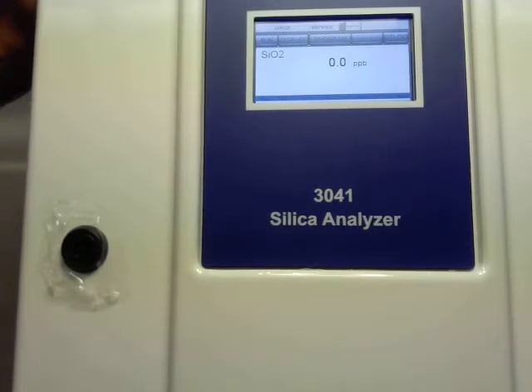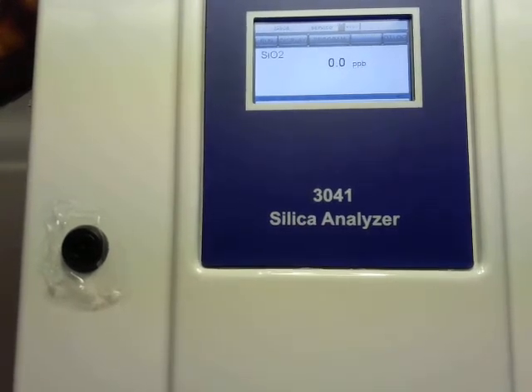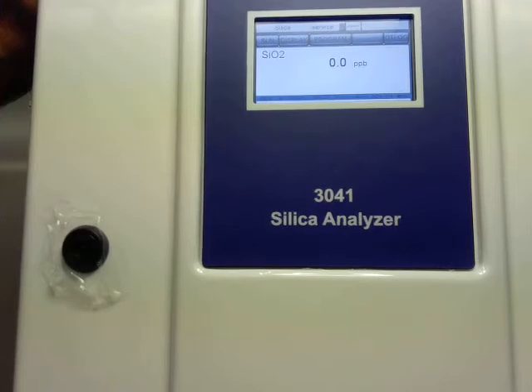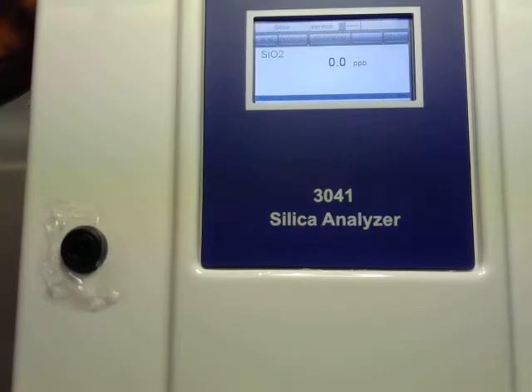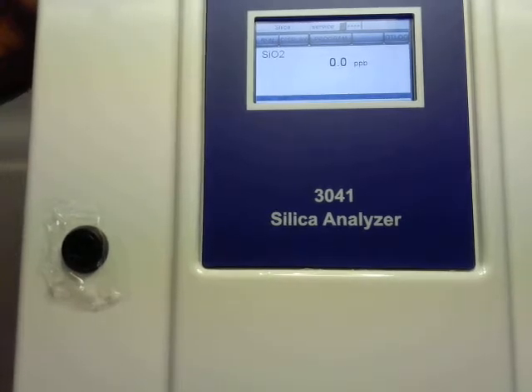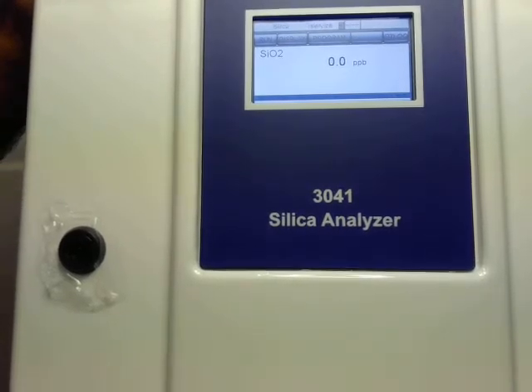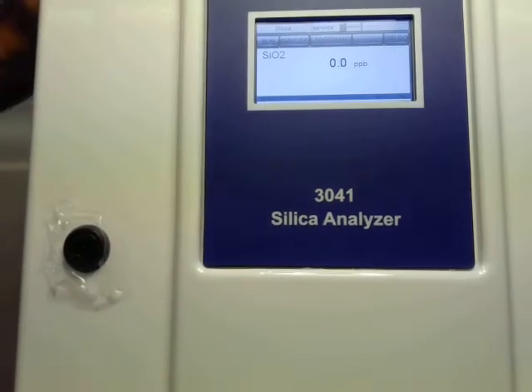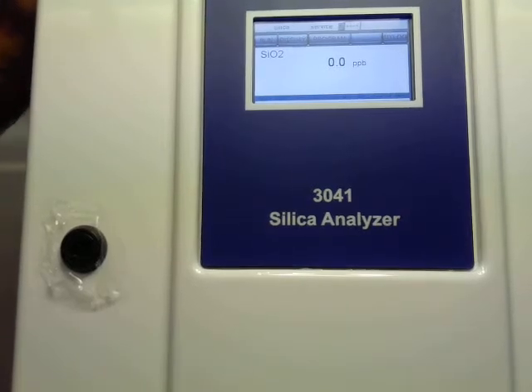The calibration standard will go at a different rate than the reagents, just based on calibration frequency and so forth. So that one doesn't have a percentage counter on it, and it's up to you to do your visual checks and make sure that you don't run out of cal standard. Obviously, it's good practice to replace it when you replace your reagents every month, unless for some reason you ran a lot of manual calibrations in that month. Otherwise you will have plenty of standard to run your auto cals.